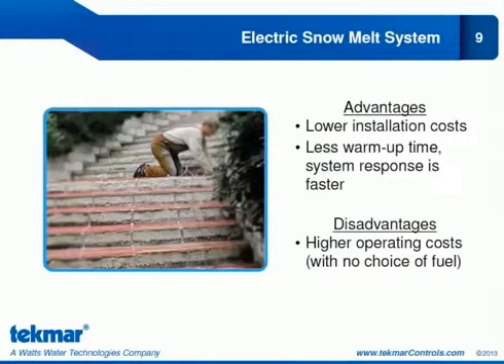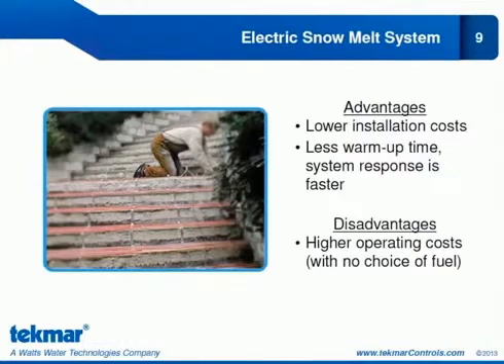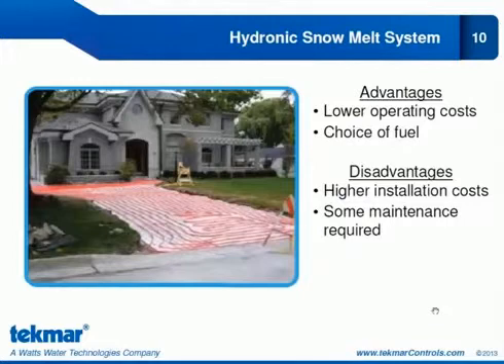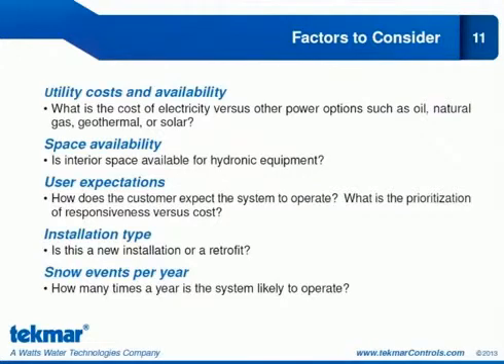The advantages of having an electric snow melt system include a lower installation cost and a reduced warm-up time, meaning you'll have a faster system response. The disadvantage of an electric snow melt system is that you have no choice of fuel — you are stuck with your electrical utility and are very susceptible to changing rates. The advantages of a hydronic system are that you have your choice of fuel, including alternative methods such as a high efficiency boiler, solar, or geothermal, which lowers your operating costs. The disadvantage of a hydronic system is a higher installation cost and potential maintenance requirements.